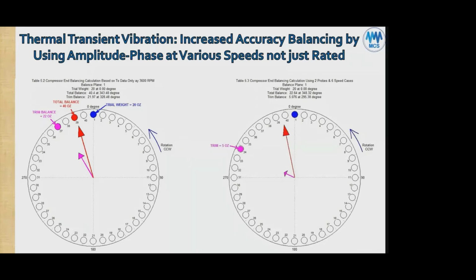He recommended, if you notice on the left-hand side, compressor end, this is the gas turbine compressor end bearing, balancing calculation based upon temperature data at 3,600 RPM. Balance plane 1, trial weight added was 20 ounces at 0 degrees, okay? And total balance needed, according to the balance calculator, was 40. So with a trial weight of 20 ounces, they found that it's not doing the job well enough. So the balance program is saying, make a total balance weight of 40 ounces at this location, and then a trim balance of 21 ounces to the left.